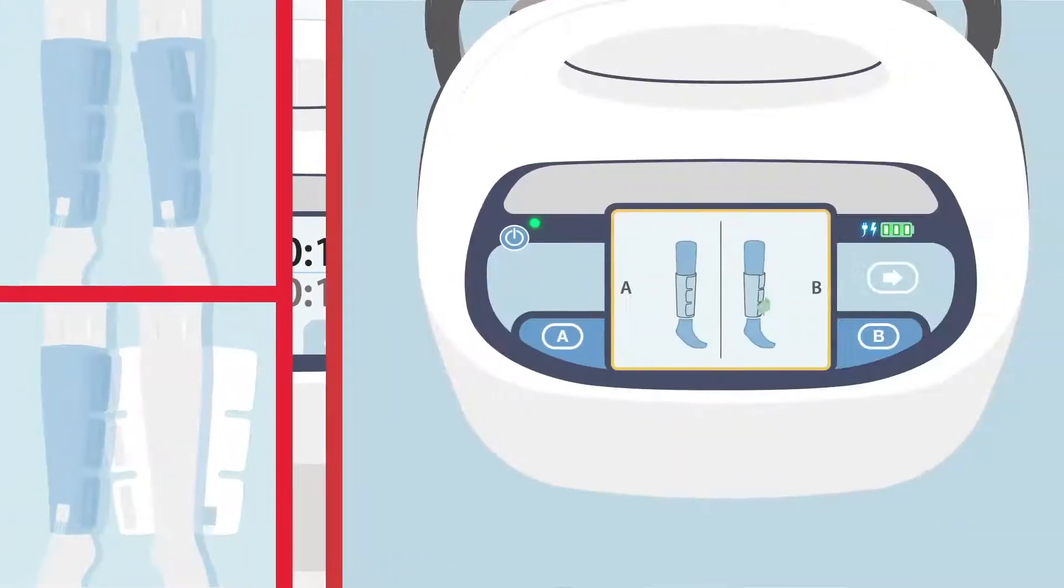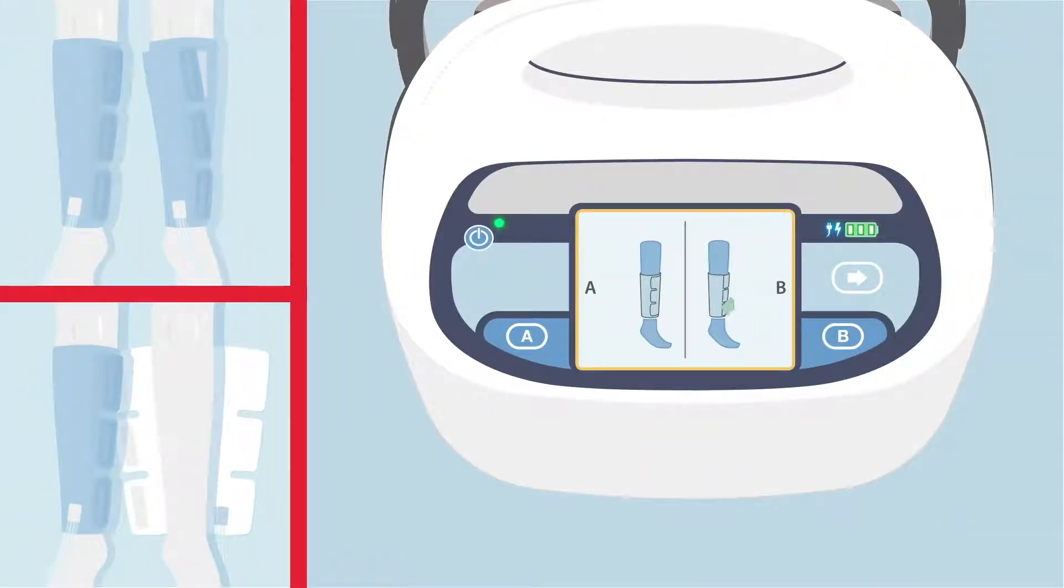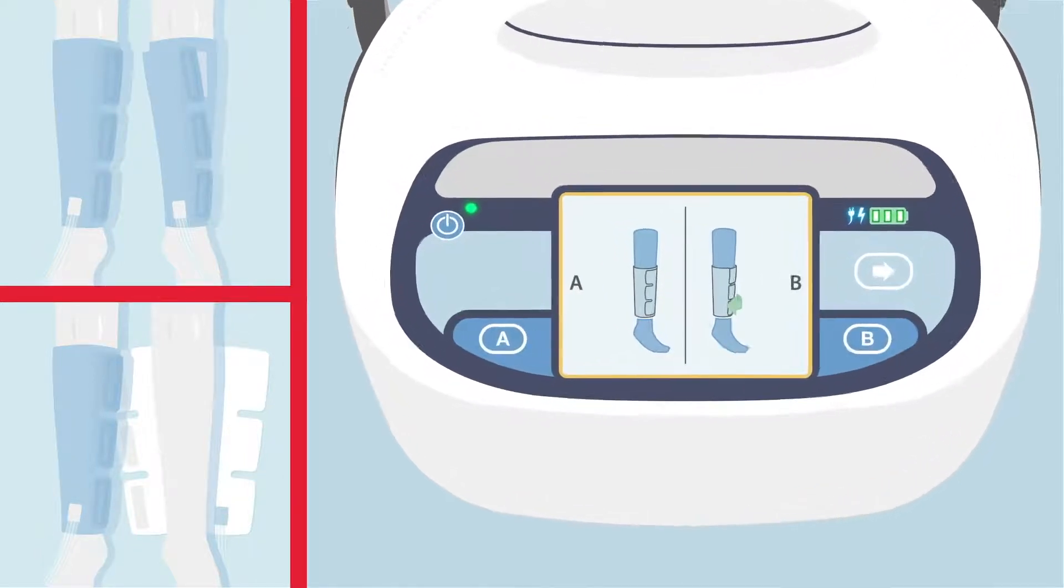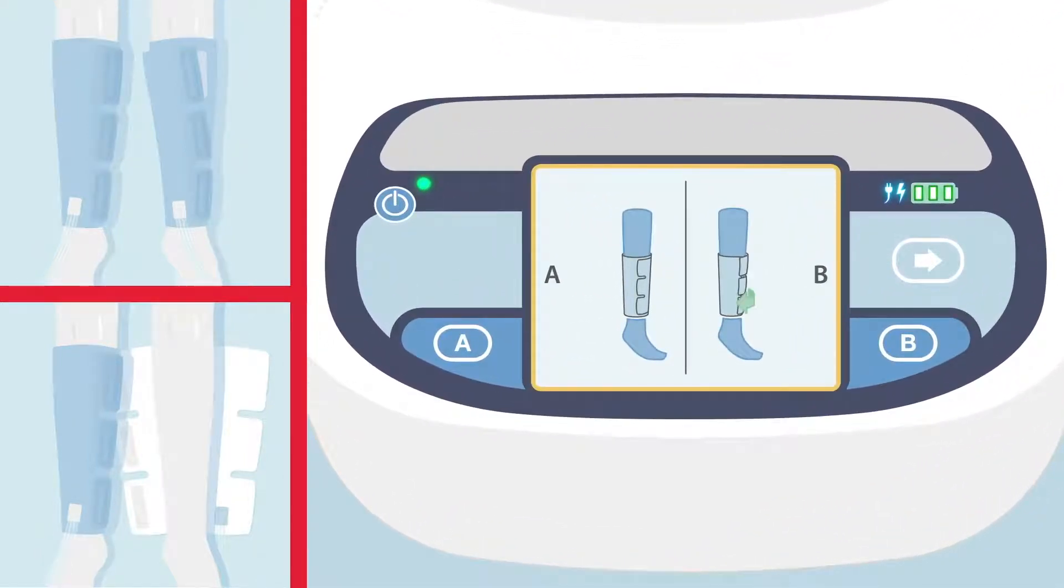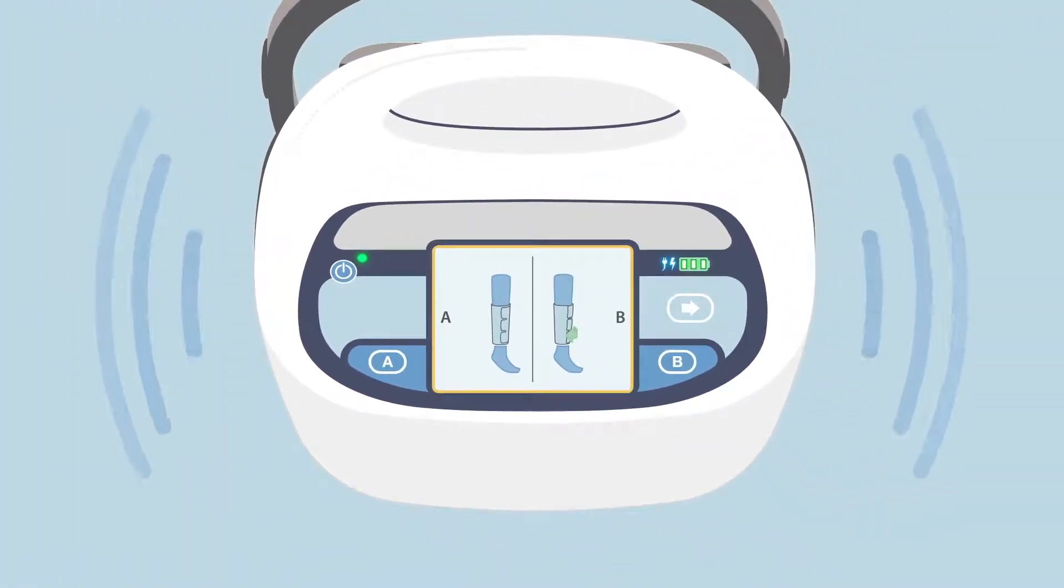If the patient takes off the sleeves or the sleeves are not wrapped properly, on the next 30-minute cycle, the pump will display that the patient is not detected and it will make an intermittent beep to notify the provider.